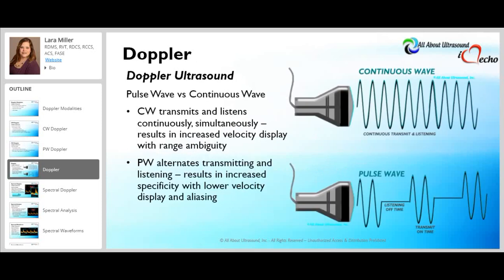When we compare pulsed wave Doppler to continuous wave Doppler, pulsed wave alternates the transmitting and listening time, whereas continuous wave transmits and listens continuously and simultaneously. This fundamental difference leads to different artifacts associated with each Doppler modality: range ambiguity is specific to continuous wave Doppler, whereas aliasing is specific to pulsed wave Doppler.